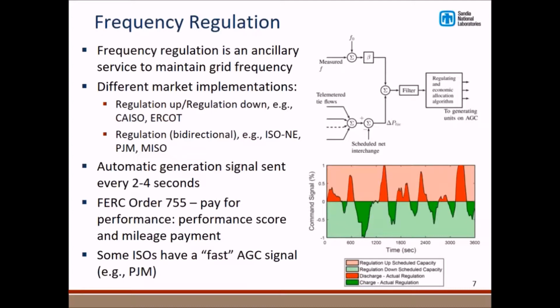Cal ISO breaks it up into regulation up and regulation down, so it's two separate markets, one for each direction. Other places it's bidirectional, so they assume you can go both ways, and ISO New England is one of those. The way this works, there's an automatic generation signal sent every 2 to 4 seconds to generators or devices that are signed up for frequency regulation.